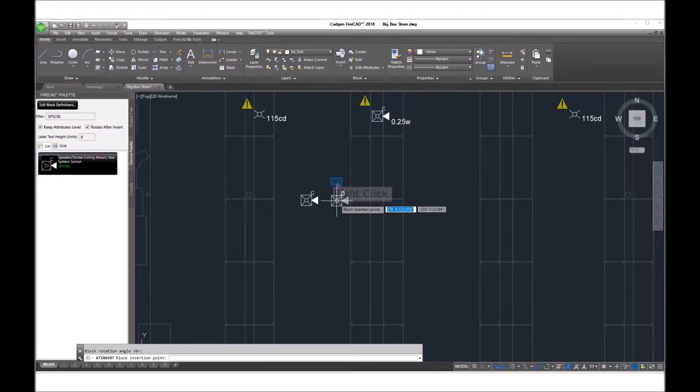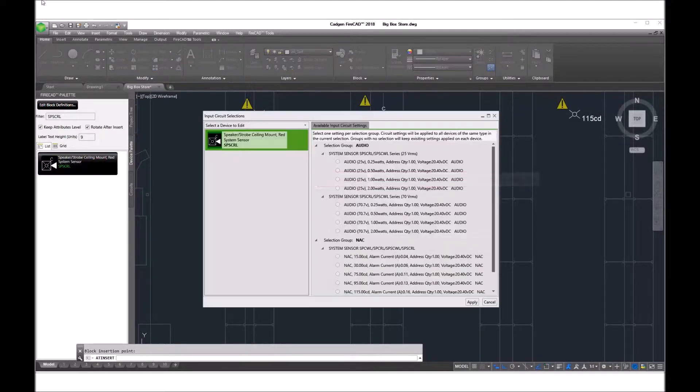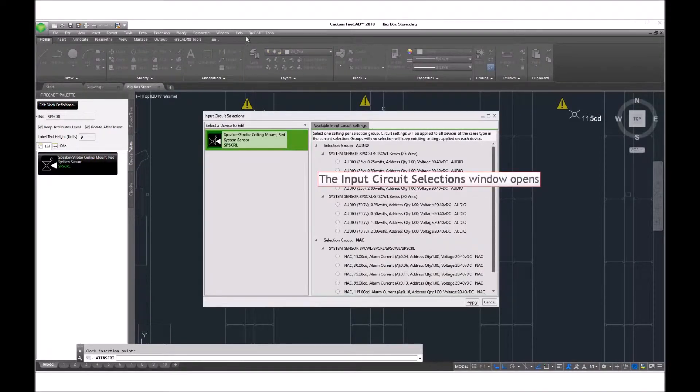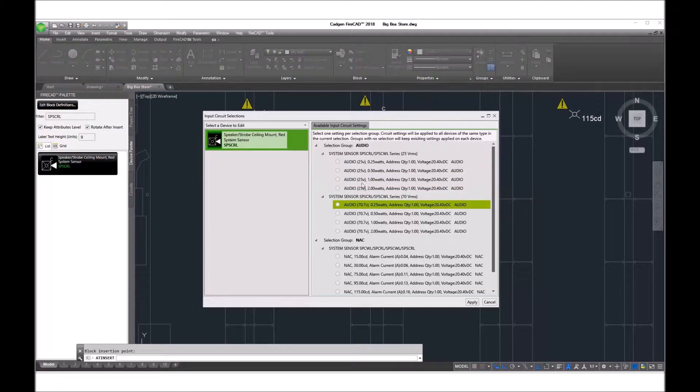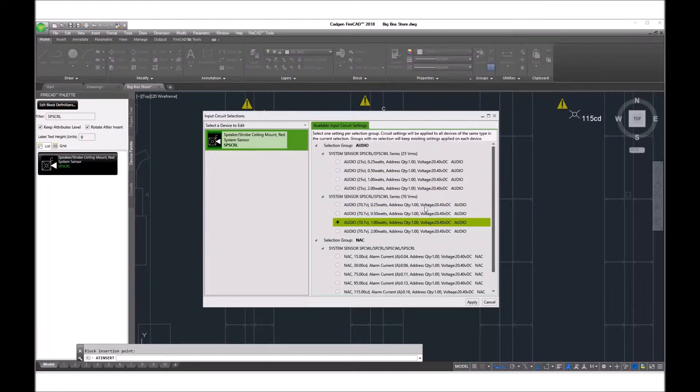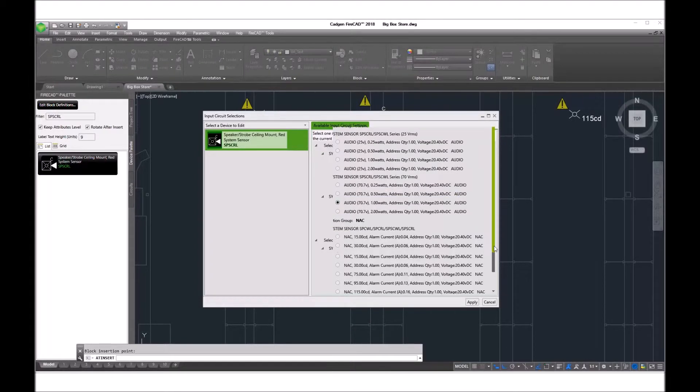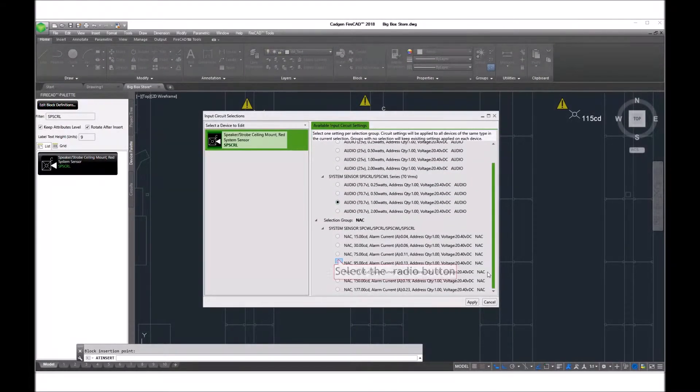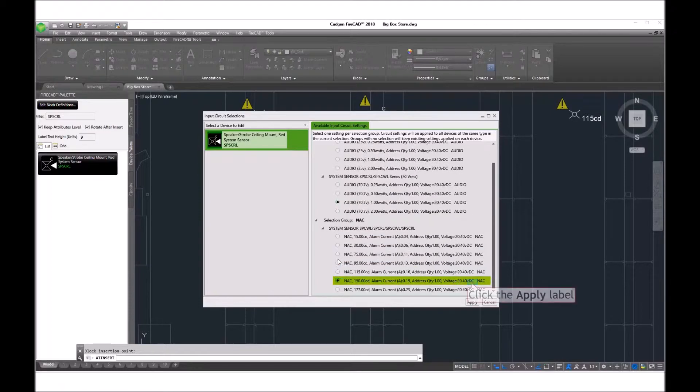In placing it on the drawing, FireCAD gives us the opportunity to set the candela setting and the speaker audible wattage tap. We do that. These settings, of course, can be changed later.